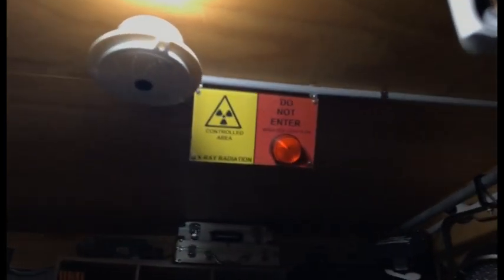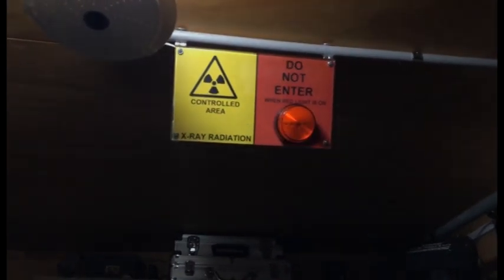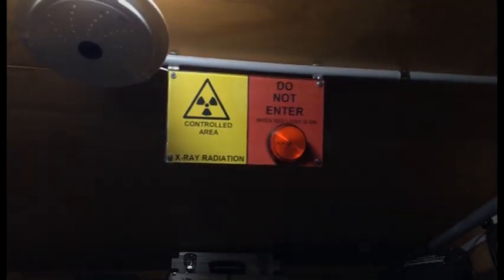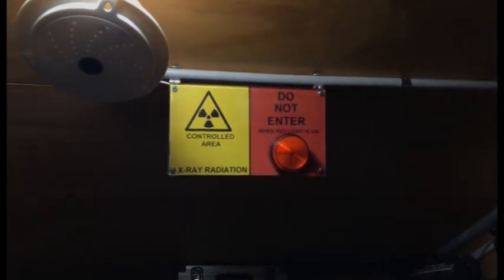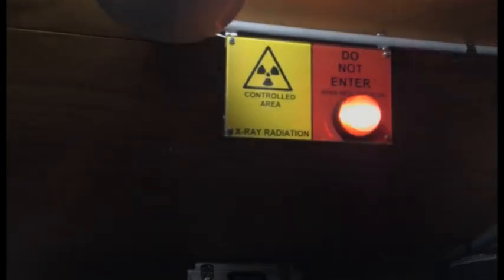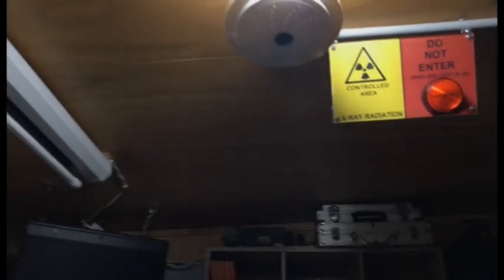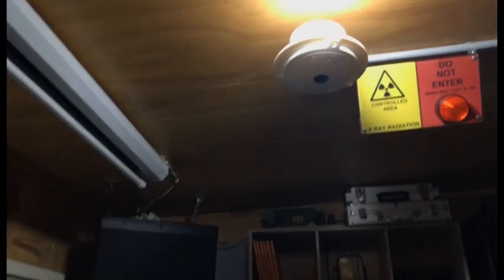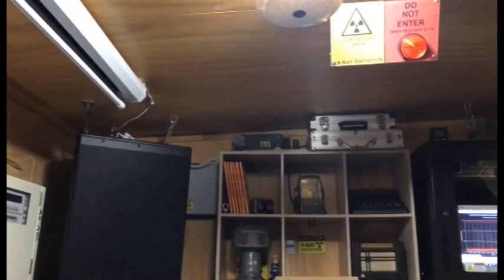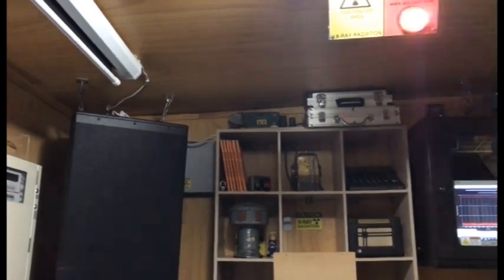And you will see the strobe begins to flash. Here's the audio alarm. And in a couple of seconds, the X-ray head would turn on and begin to image. Okay, I just heard it click, and you can see this is now shooting the image.